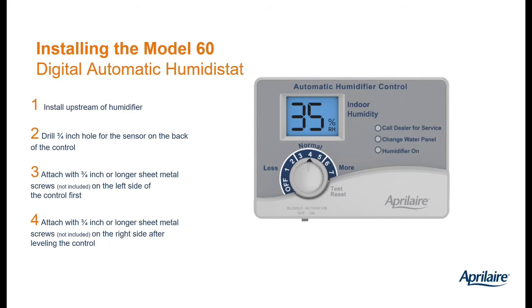You're going to drill a hole in the duct so the relative humidity sensor on the back will protrude into the ductwork. There's a little dome on the back that protrudes into the ductwork with a seal that seals up that hole, so you're not going to get any air pulled in. And then you just secure it with sheet metal screws.